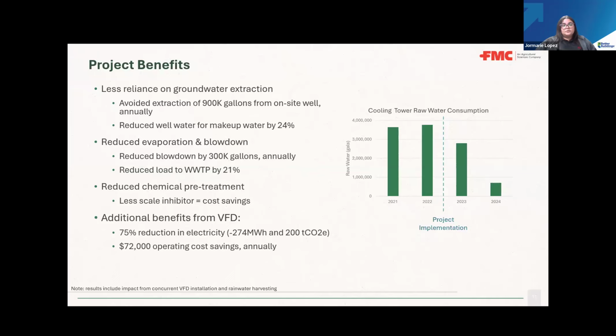In addition, this results in 300,000 gallons less blowdown water per year, which lowers the load to the wastewater treatment by 21%. The reduced mineral content in rainwater decreased the need for chemical pretreatment and scale inhibitor, leading to cost savings. Additionally, the VFD reduced the electricity consumption by 75%, which is equivalent to 274 megawatt hours, and reduced 200 metric tons of CO2 emissions, and also saved $72,000 annually on operational costs. So using rainwater for the cooling tower makeup water brings environmental and financial benefits, including reduced water usage, lower energy consumption, and significant operating cost savings. Next slide.